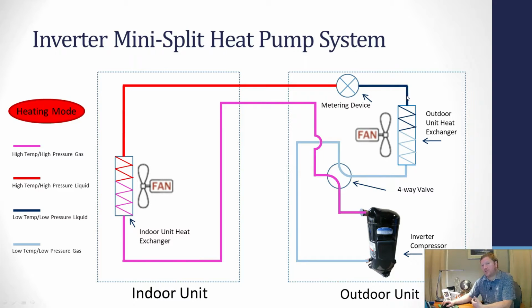That liquid then goes through the outdoor unit heat exchanger and needs to absorb the heat energy from outside. So the goal that this expansion valve has is to get that liquid temperature 10 to 15 degrees colder than the outdoor air. That way when it goes through the outdoor unit heat exchanger, it can pull that heat energy out of the outdoor air. And by the time it leaves that heat exchanger, it should be that light blue line, which is a low pressure, low temperature gas going back to the compressor. This is the same thing a traditional heat pump system does. An inverter system just does it better.